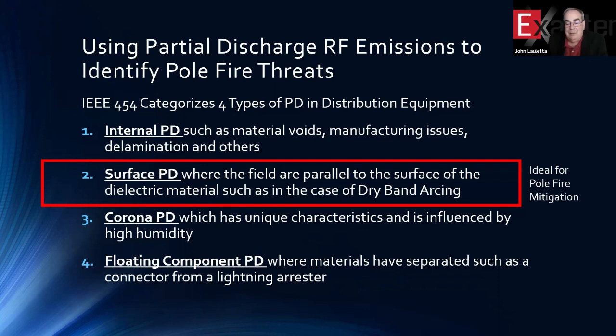And to do that, you have to be able to receive the emission, which is a VHF kind of RF signal that comes from partial discharge, but you also have to be able to understand the signal you're listening to, and you have to have a way to locate that emission source. So we've developed signatures for partial discharge, and those signatures are very specific emission characteristics. We're not just listening to RF that's being transmitted from some source, but we're listening to exactly the emission that comes from a piece of deteriorated equipment.